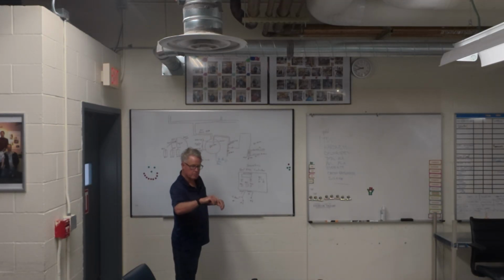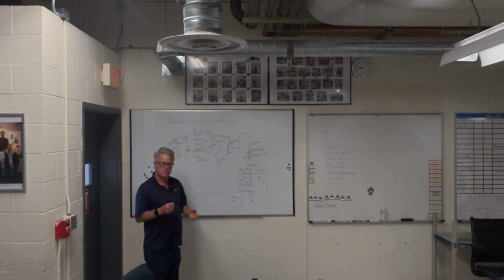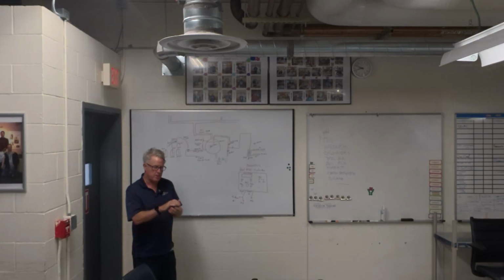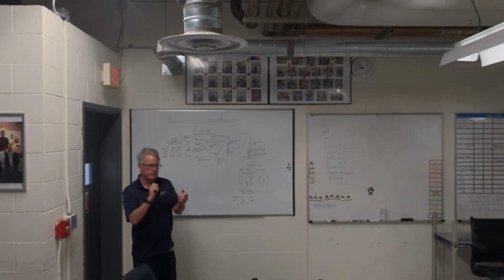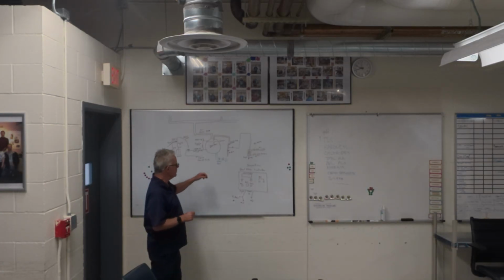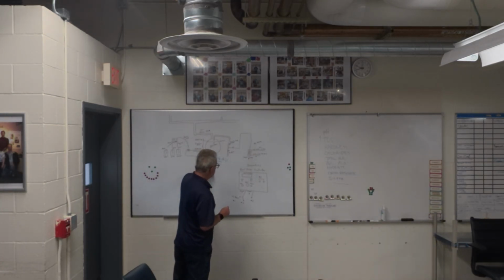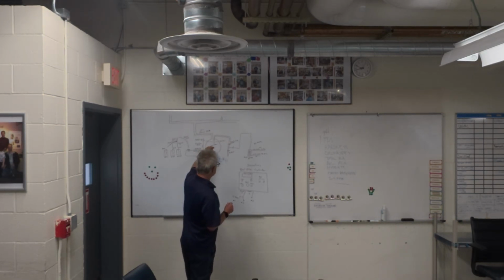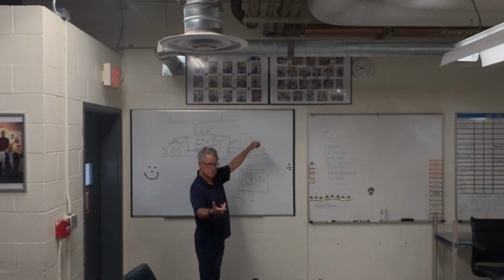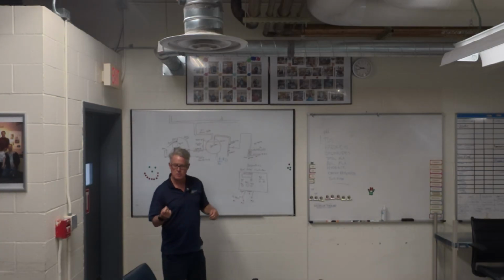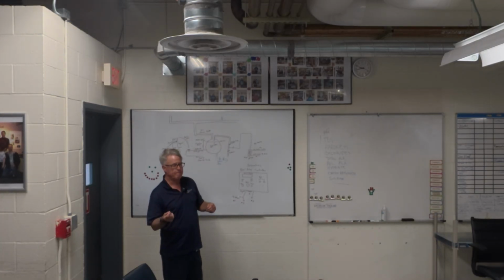Again, we can modulate it separately with the feeds, but in those cases, we're using degassing pumps, because if you don't use a degassing pump and you put it in the heads of these pumps, they would just degrade them very quickly. And so you need a degassing pump. Some of the other chemicals you can interrelate, but for the most part, that's why you see degassing pumps. So the steam goes to your autoclaves, which you're measuring, right? And Pete and I started the program here where they're measuring actually the quality of the steam in the autoclaves to prevent the corrosion.